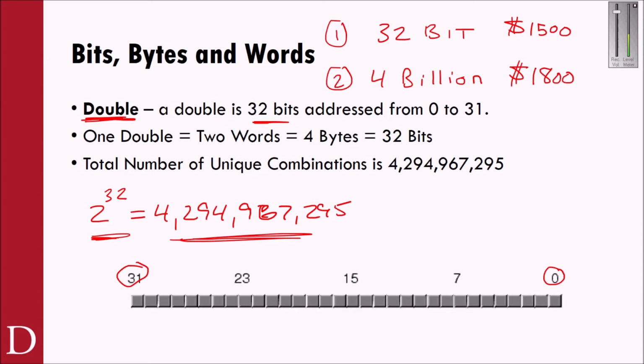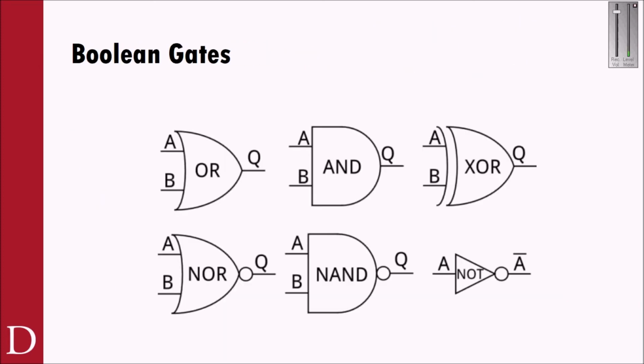So anyways, a double is another type of addressing system. And as we go from 16-bit to 32-bit, some of our newer computers and our newer PLCs will actually be 32-bit. What does that mean? Well, that means now a counter might count to 4 billion, or half, plus or minus 2 billion, right? So I can go to negative 2 billion and positive 2 billion. But it gives you again an idea of why the size of the collection of bits is important to us.